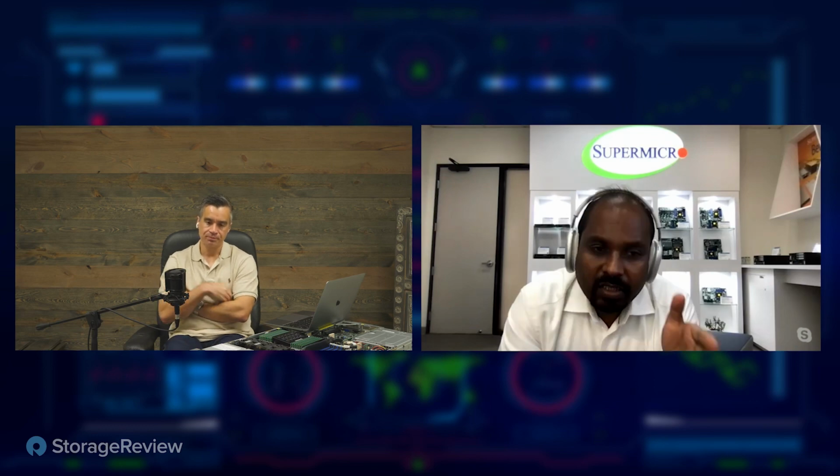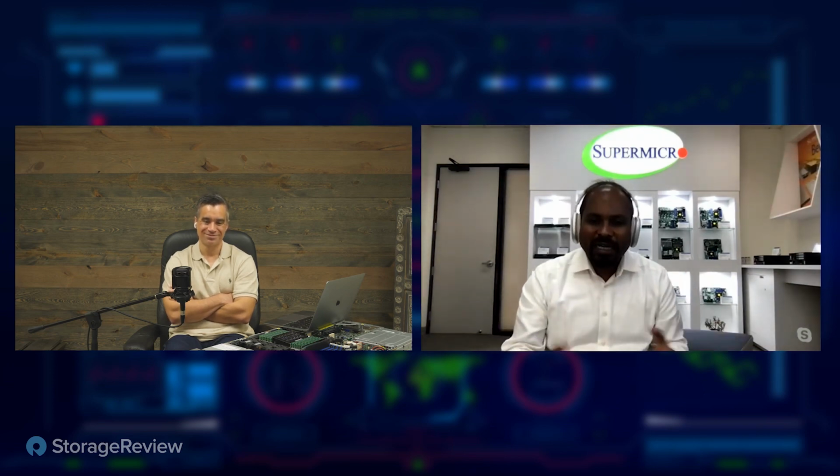Various things, right? I think, definitely that's one of the advantages, but even more so, if you take a look at the standard PCIe form factor double width card, it's about 300 watts. And mind you, now we are talking about accelerators. People are bringing it to 600, 700, 800 watts per card. And it's impossible to support that in a traditional double width PCIe slot. Maybe we can make it even bigger and have extra power, but it just becomes too bulky. Versus having this OAM form factor, or from the NVIDIA point of view, their own mezzanine card form factor, right? These are the ones that can accommodate a higher wattage, and much of the interconnect between them is in the board as we design the board for that. It makes it easy for us to cool it by liquid cooling, or by putting a bigger heatsink in a bigger enclosure to do that.